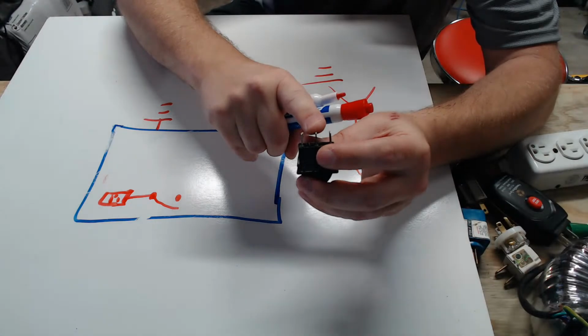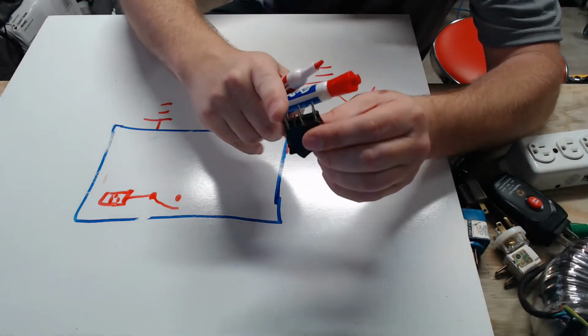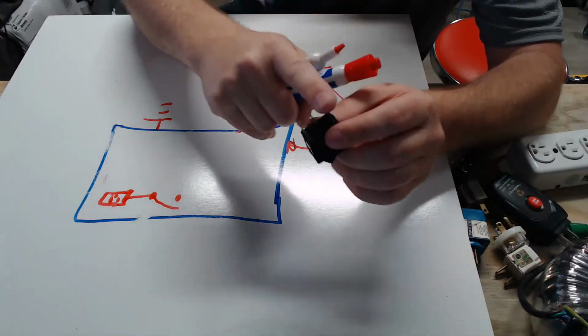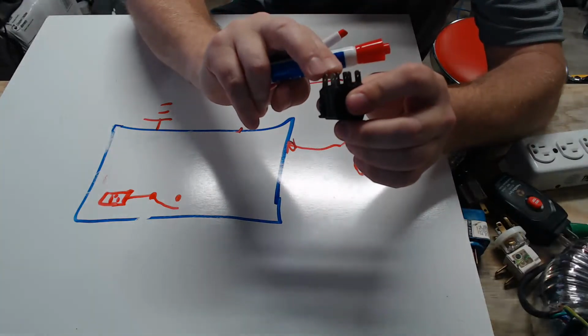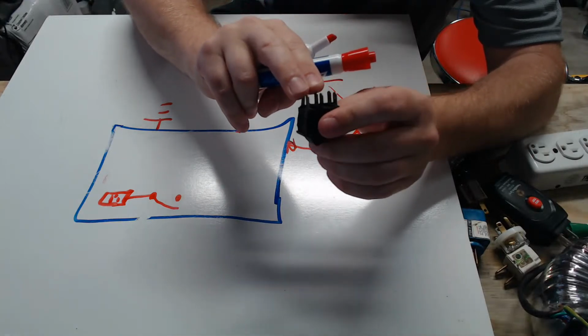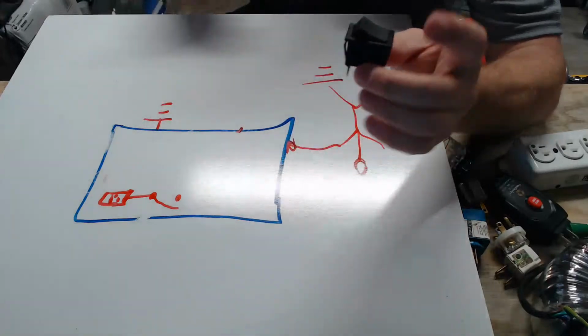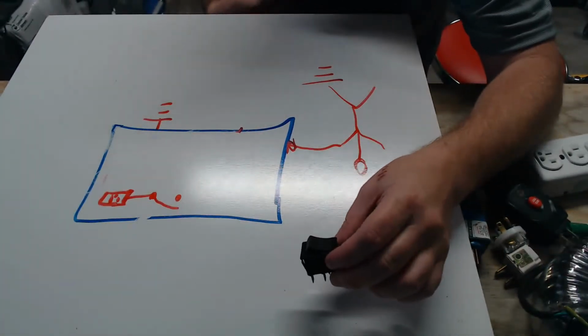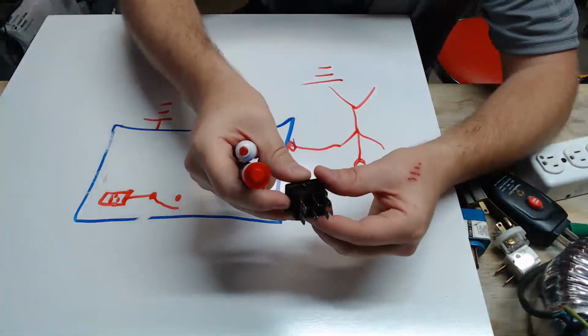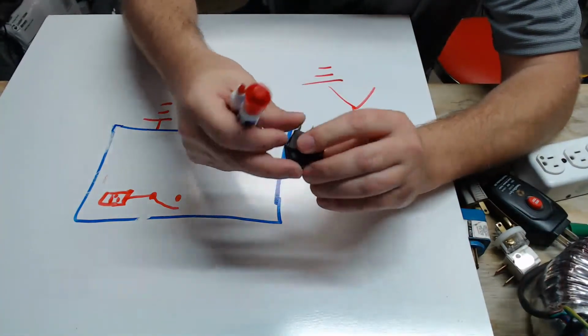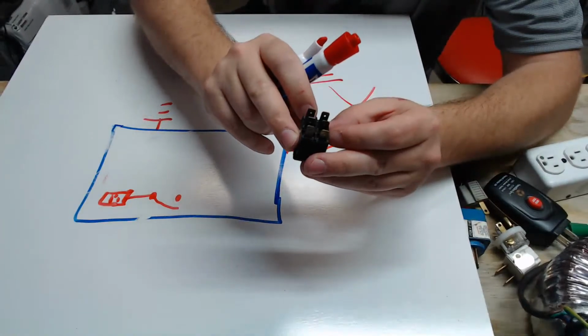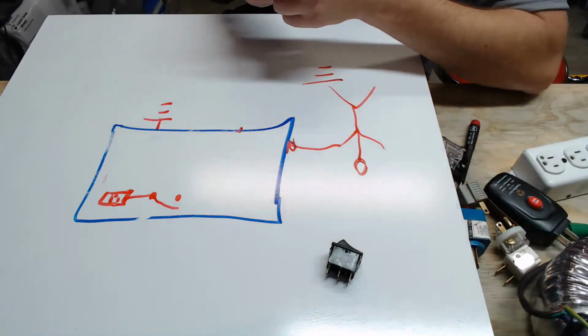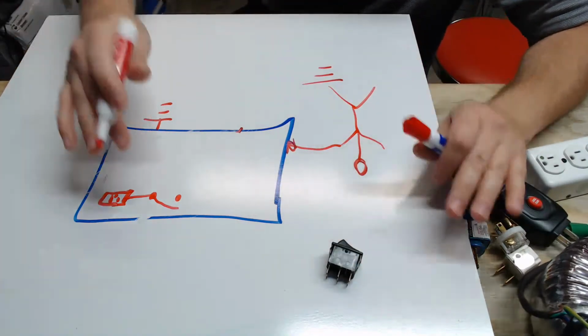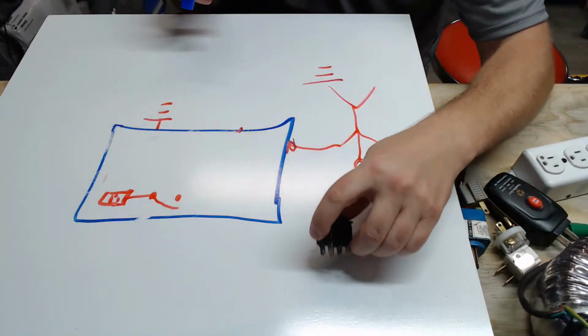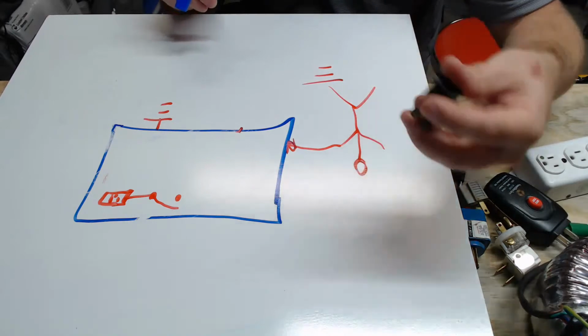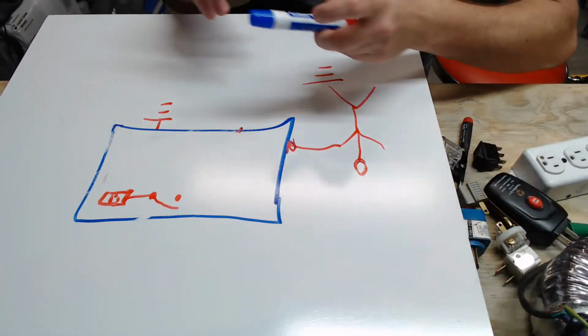Normally the middle is common. Okay. So when you flip it off, it's going to some open connections here. When you flip it to on, it makes these two right here connected. All right. So this is a traditional power switch used in medical equipment. Okay. Maybe you guys can see it a little bit better there. So this type of power switch right here is what we usually find. And that means that both your line and your neutral are cut off when you hit the power switch. But that is not always the case. We'll go into that in just a moment.